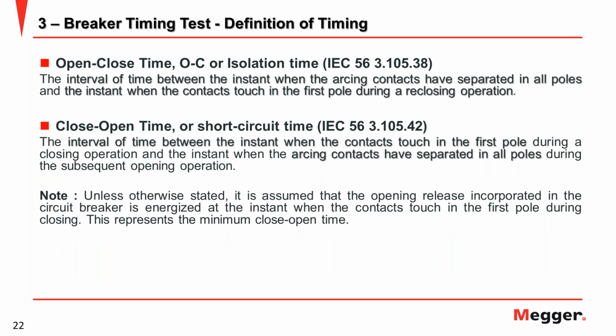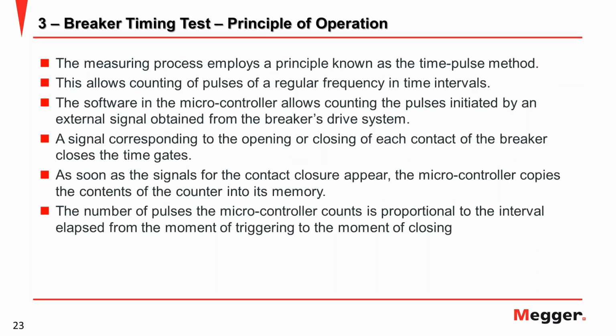And this is also an explanation about the open-close time. So all these operations should normally be tested for the breaker timing test. There are five operations: open, close, close-open, and open-close-open. Yeah, basically this is the principle of operation.